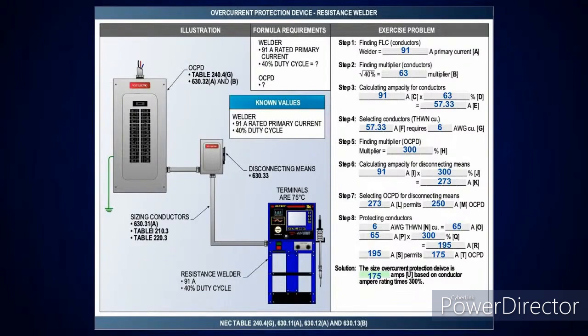Okay. Right. Now I'm going to do a resistance welder, and I'm going to do it with the full calculation with the amperage and everything. If you're doing resistance welders, you're in Part 3. So you're going to be looking at table 630.31(A) when I do it based on the duty cycle. And for my overcurrent protection device, I'll look at 630.32(A), and it's going to tell you there to take it at 300%. So remember, for non-motor and generator type arc welders, you take it at 200%. For a resistance welder, you do it at 300%.